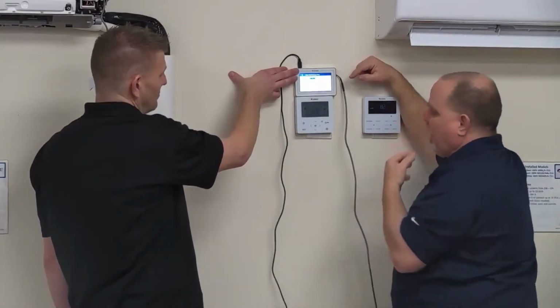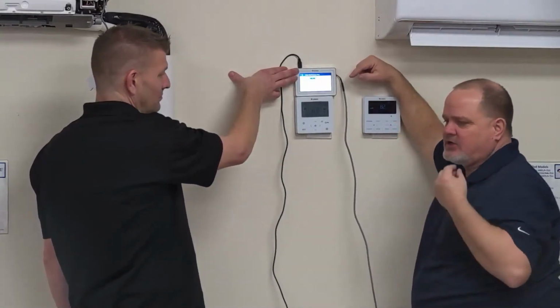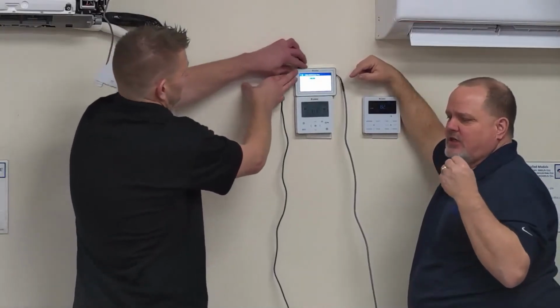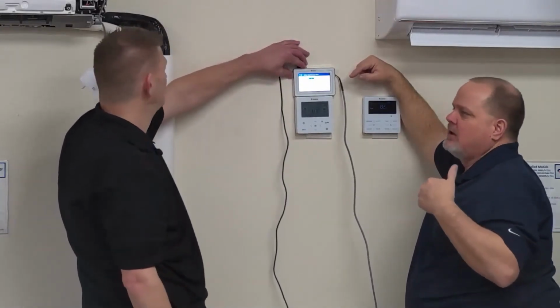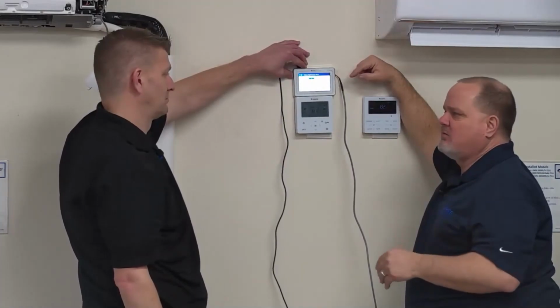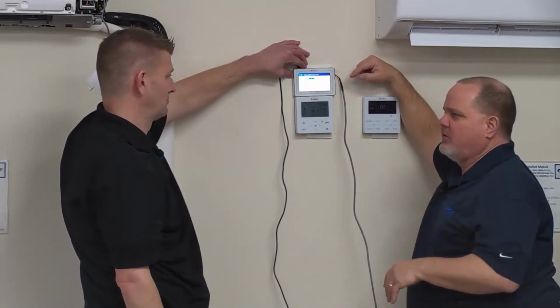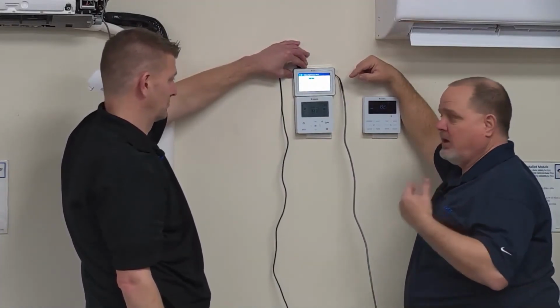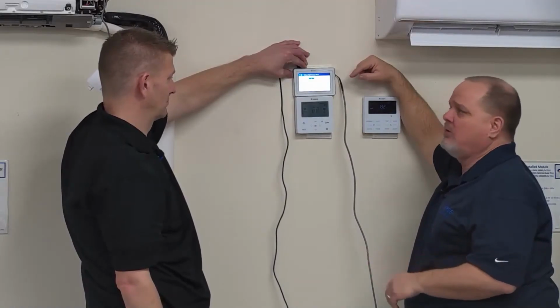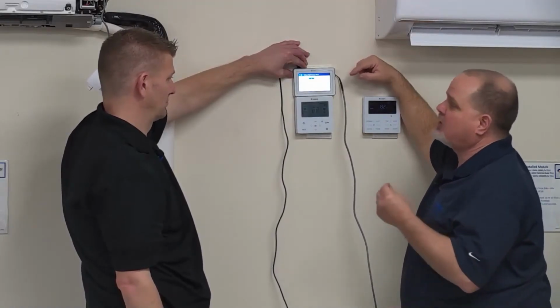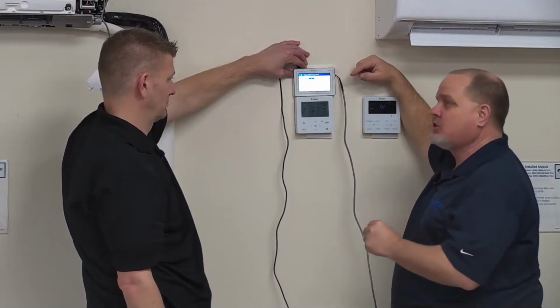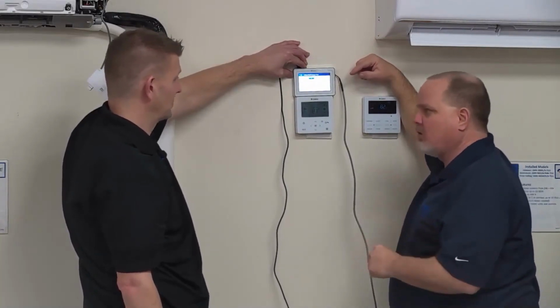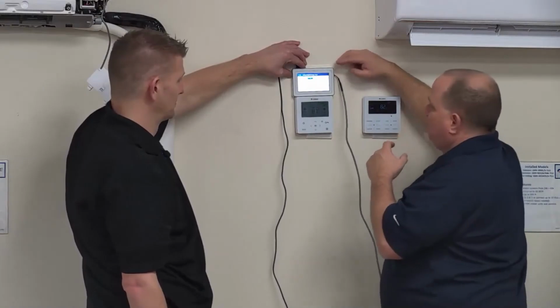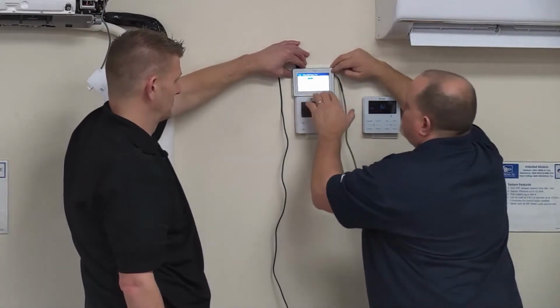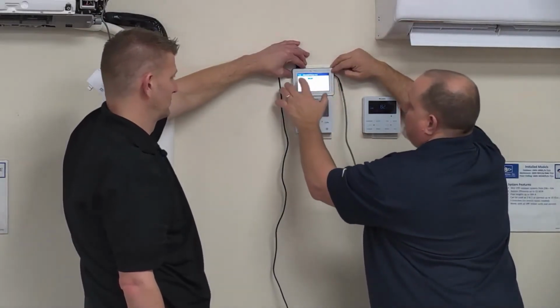Now, I always say, to me, it's a lot easier to do refrigerant diagnostics in cooling mode. And these machines will run in cooling mode all the way down to 0 with no problems. So when in doubt, check it out. Run it in cooling mode. That may make the refrigerant diagnostics easier for you. Good point. So anyway, that's a good differential.